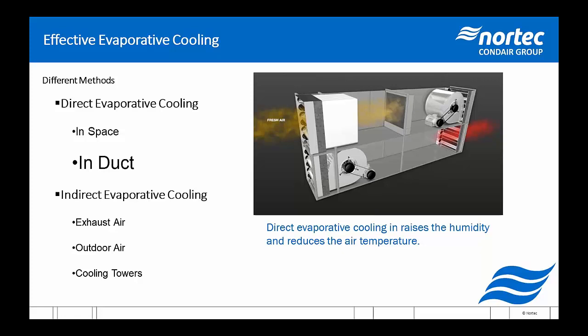We have a question about the quality of the water for evaporative humidification. So there's different evaporative humidifiers for high pressure and DL systems, the DL being the dual humidifier that uses a pressurized water and a media. Both of those require reverse osmosis or better water. For systems such as the media evaporative, the ME system, we can run that on potable water. Similar to how steam humidification works, generally the better the water quality, the less maintenance is going to be required. So generally RO or better is what we recommend, but with some systems, compressed air and media evaporative systems, we can use RO or potable water.